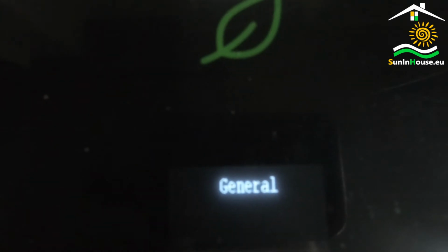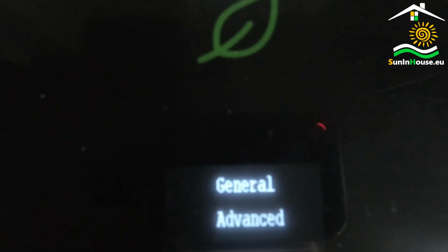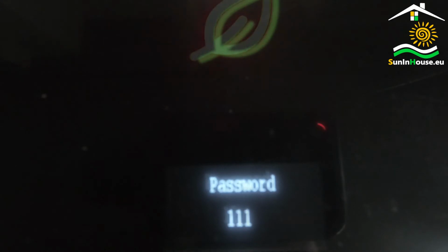This is the size of the short-term maximum and minimum AC voltage range on all phases. We have three levels: standard 0, 1 wider limits and 2 the widest limits. Depending on the parameters of the supply network, we select the appropriate level. Any errors in the AC voltage signal that this setting is too low a level. By default, level 1 is selected.